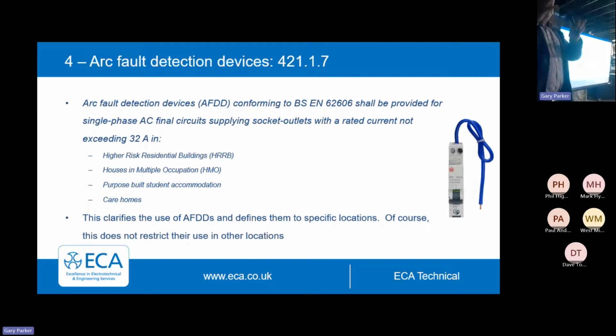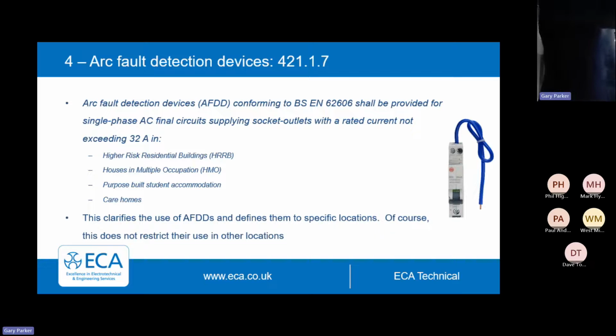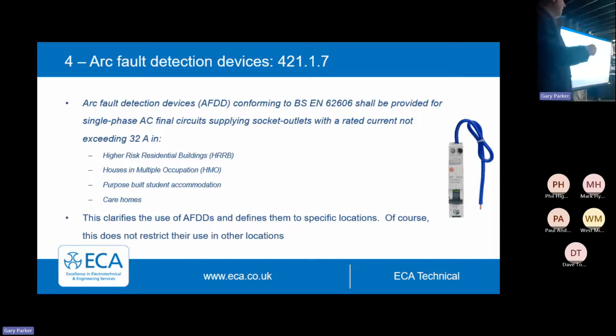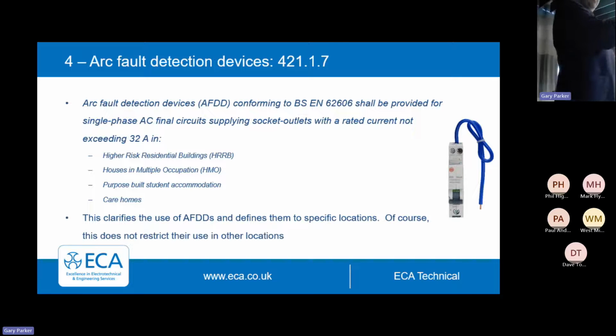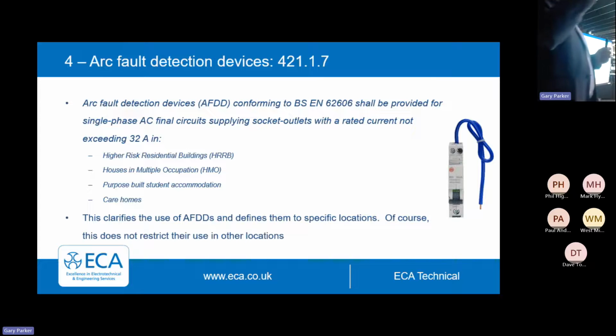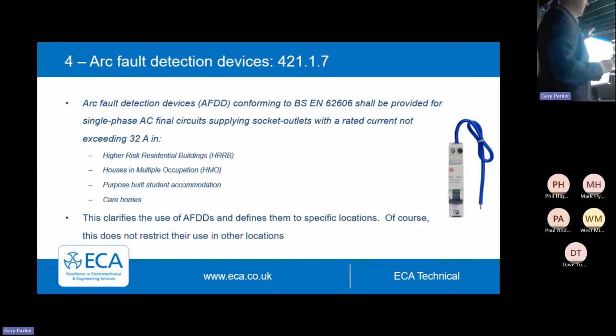Then you had a different make where yellow was good. So that was nice and complicated when you're trying to speak to a client about a fault. Some of them had a solid light. Some of them had a flashing light. And then some of them, when they went into fault, had a flashing light. One of them, when it goes into fault, has a flashing light for 3 seconds and then stops flashing. Now that flashing light for 3 seconds means something. But if you don't see it, you can't really diagnose what the problem is. That's a bit silly and a bit pedantic to me, but it's annoying.